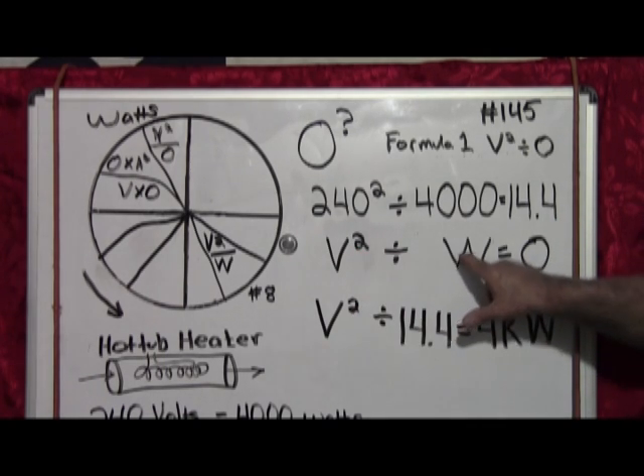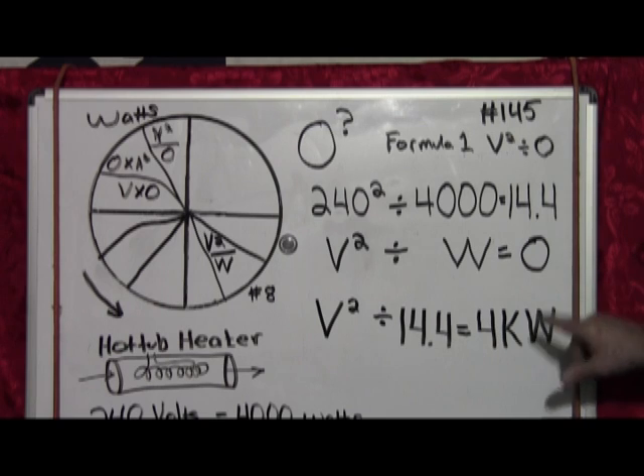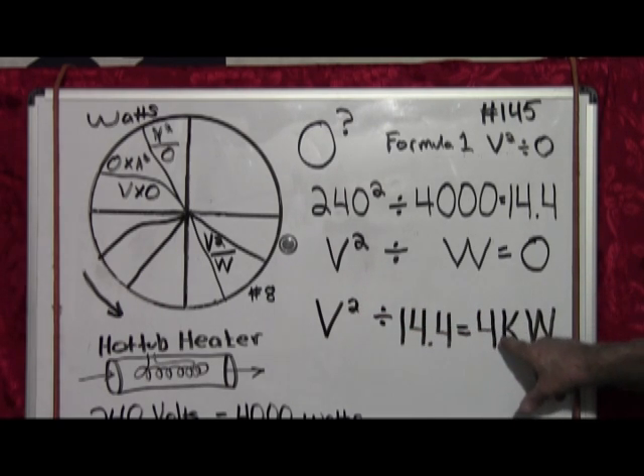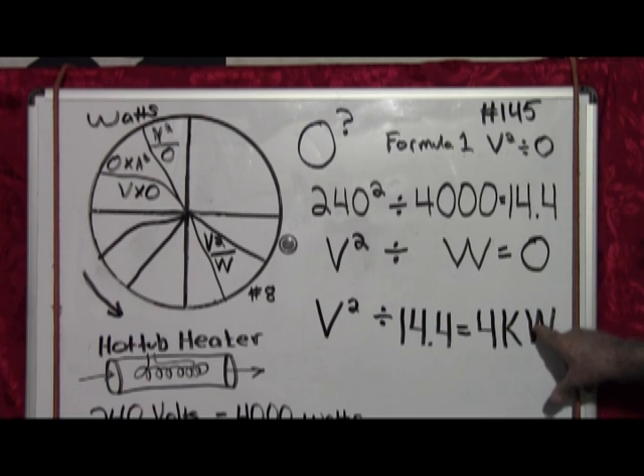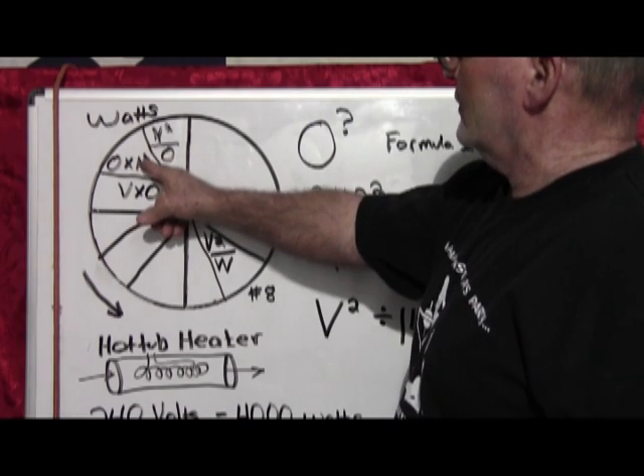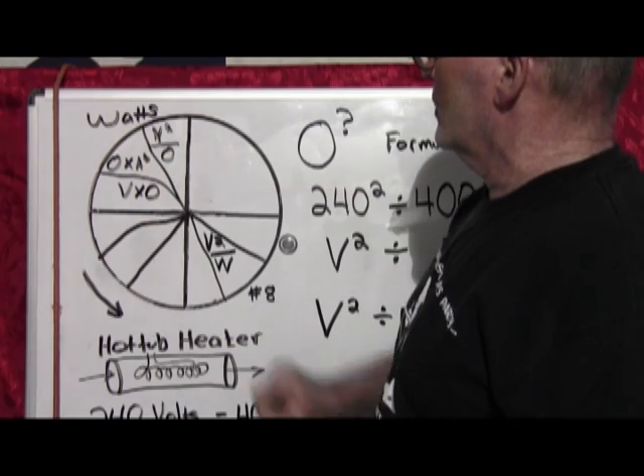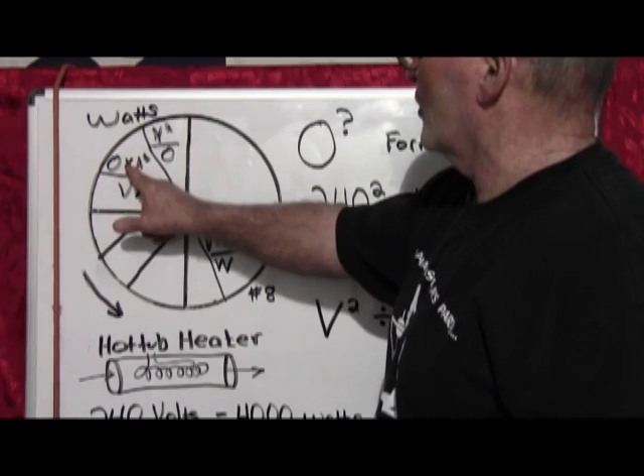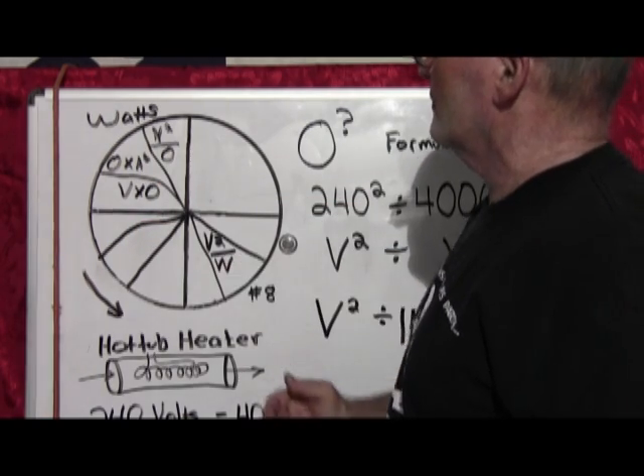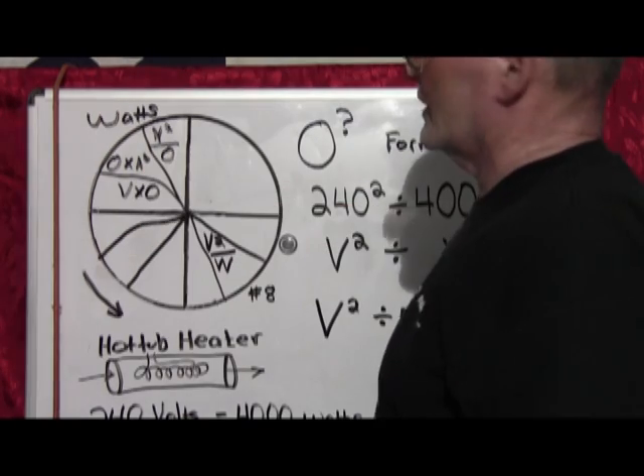So volts squared divided by watts equals ohms. V² divided by 14.4 is equal 4 kilowatts or 4,000 watts. That solves for equation number one. Let's move on to equation number two, which is ohms multiplied by amps squared will give you watts. Well, we've got to solve for amps, don't we? That's not a problem.